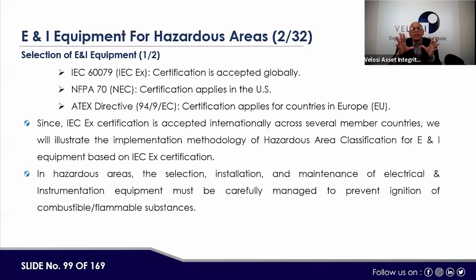Now, the point is, this is not for the certification of the people, this is certification of the equipment in accordance with the applicable class of the hazardous zones. Since IEC Ex certification is accepted internationally across several member countries, we will illustrate the implementation methodology of hazardous area classification for E&I equipment based on IEC Ex certification.